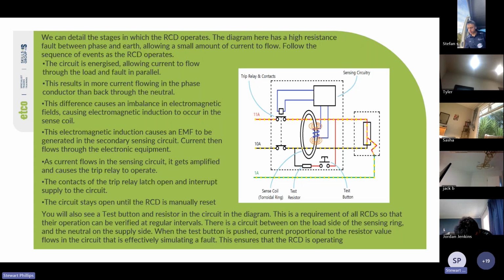The difference causes an imbalance in electromagnetic fields, causing electromagnetic induction to occur in the sense coil. The electromagnetic induction causes an EMF to be generated in the secondary sensing circuit. Current then flows through the electronic equipment. As current flows in the sensing circuit, it gets amplified and causes the trip relay to operate. The contacts of the trip relay latch open and interrupt supply to the circuit. The circuit stays open until the RCD is manually reset.